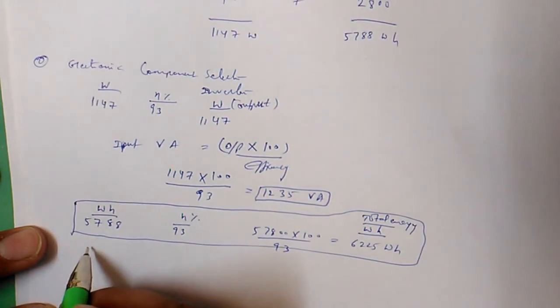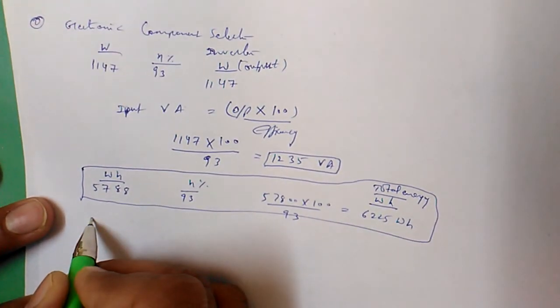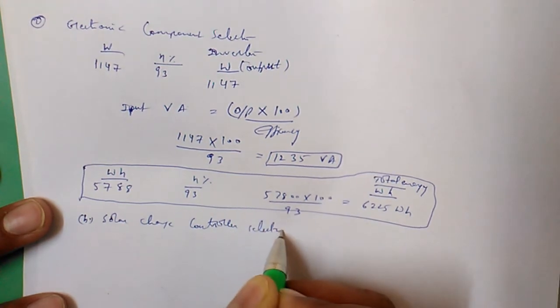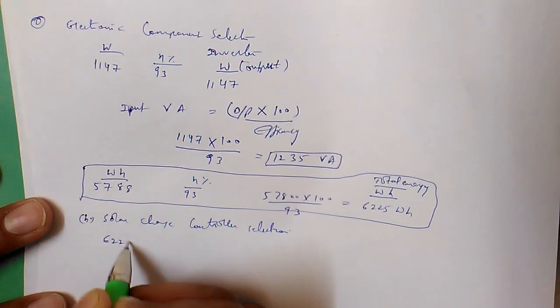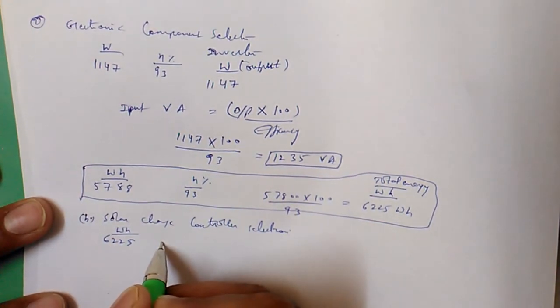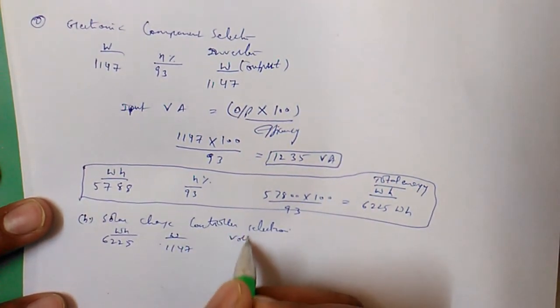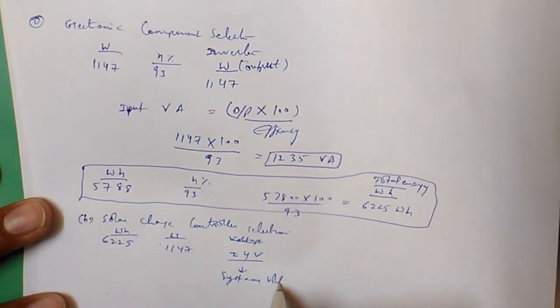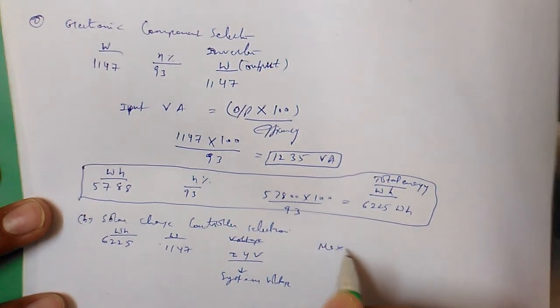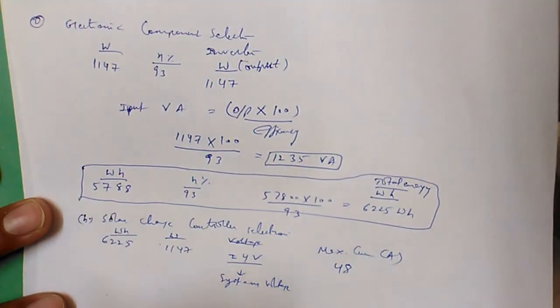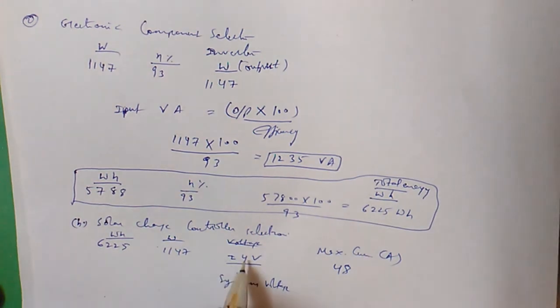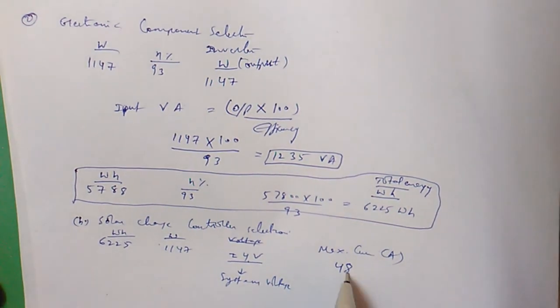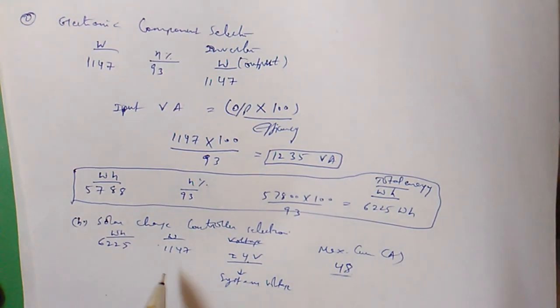Next is solar charge controller selection. Total energy is 6225 watt-hours, load is 1147 watts, and system voltage is 24 volts. Maximum current = 1147 / 24 = 48 amperes. So the charge controller specification is 24V with a maximum current of 48A.